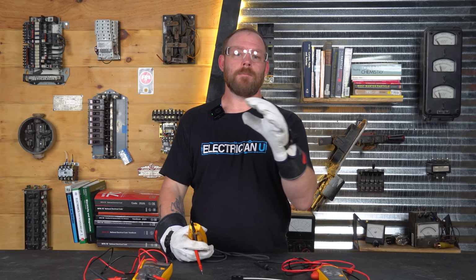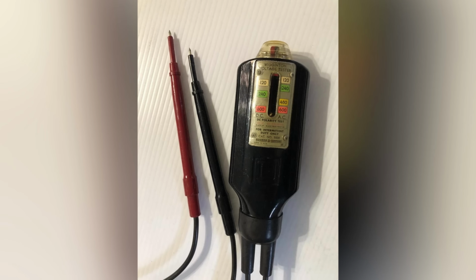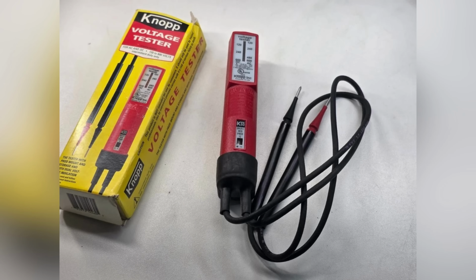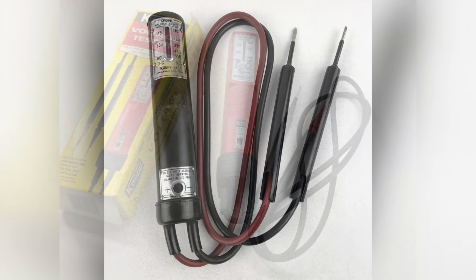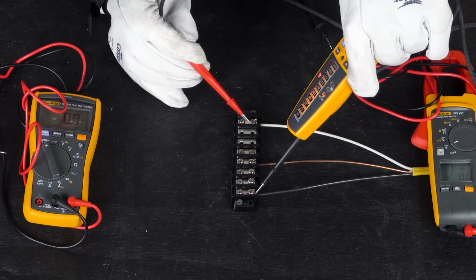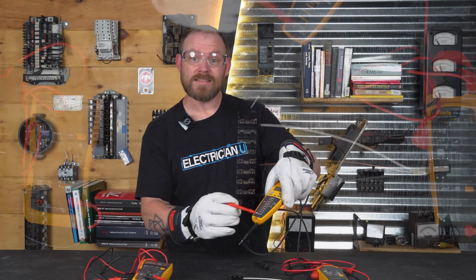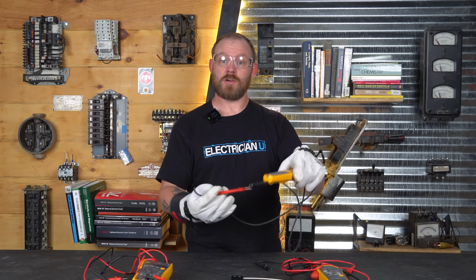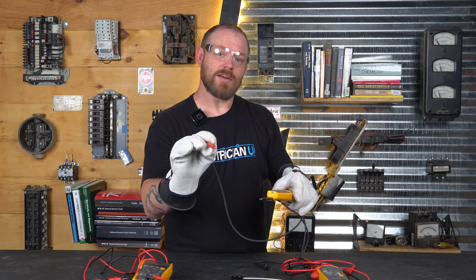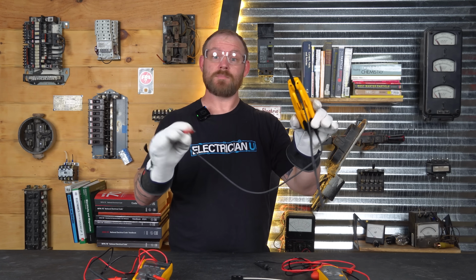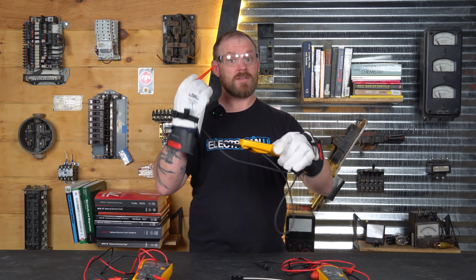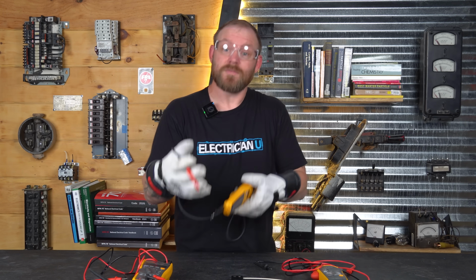So a lot of you guys, the old heads amongst you, like some of your older masters and journeymen, might have had these solenoid testers that are not digital. There's just a little wafer inside that has a solenoid behind it. And when you connect it to something, it sits and buzzes at you and screams at you, and it moves a little wafer inside, and it lets you know, like, whoa, okay, I actually have a voltage here. There's something dangerous. There's a real energized potential here. But when you had a ghost voltage condition, because that meter's making a solenoid load, if there's a ghost voltage present, it wouldn't move the wafer. So that was a really smart way for electricians to know, like, oh, I have a ghost voltage here.